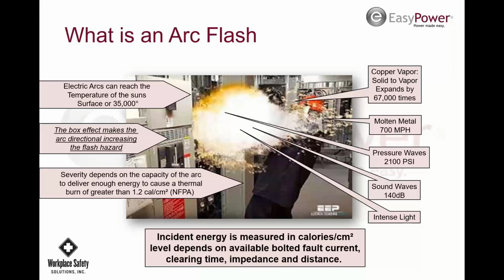And so those two things are the key parts of what needs to be collected, along with wire size and type and length and all that. But the clearing time and the fault current are some really key components of why or how big this arc flash is going to be. But the key to remember is the clearing time is directly proportional to the incident energy level.